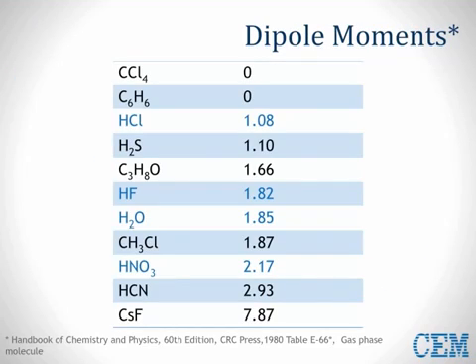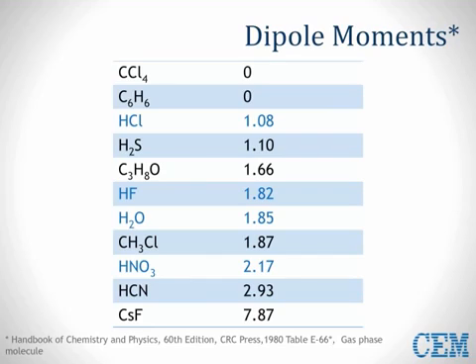There are many ways to predict if a molecule can be heated by microwave energy. The easiest is to look at the dipole moment — the stronger the dipole, the more easily it will be heated in a microwave field. In our chart, you can see that all mineral acids have a dipole moment above 1.0, and nitric acid is a super absorber at above 2.0.